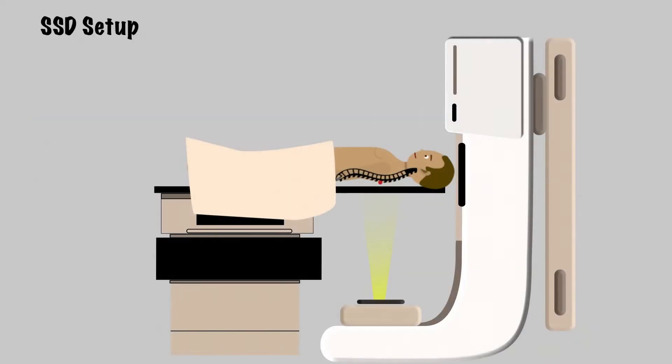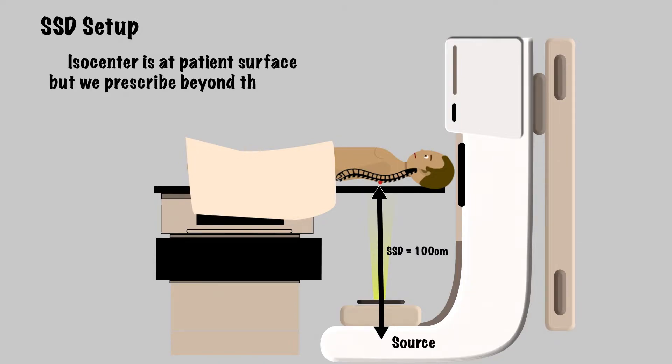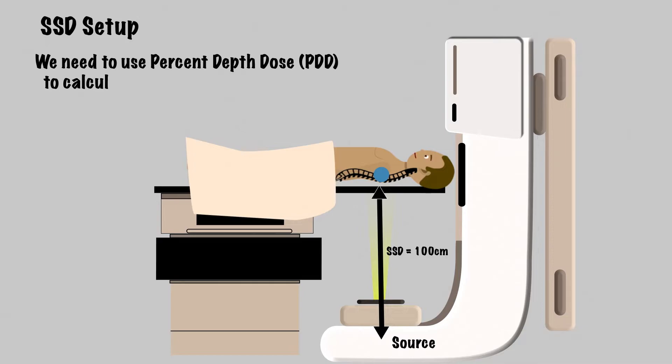When we set the isocenter, or center of rotational axis, on the patient's surface, that is what we refer to as an SSD setup. When we say setup SSD style, we usually mean at 100 centimeters. Now keep in mind, even though the isocenter is at surface for this setup, you prescribe and treat to a depth beyond the isocenter. So inverse square will need to factor in. In this circumstance, we use percentage depth dose, or PDD, for our MU calculations.